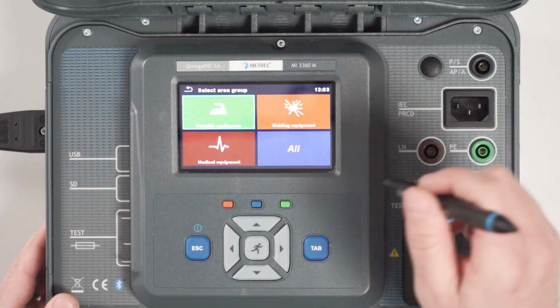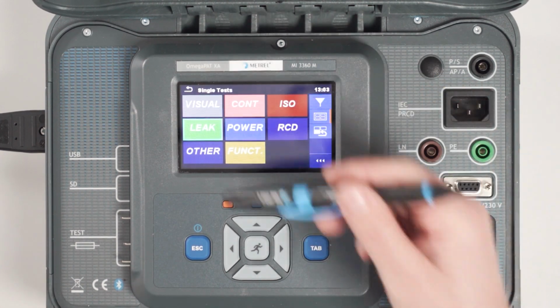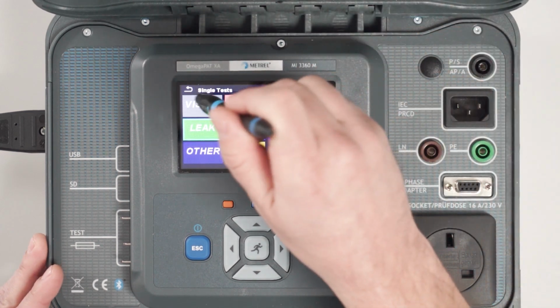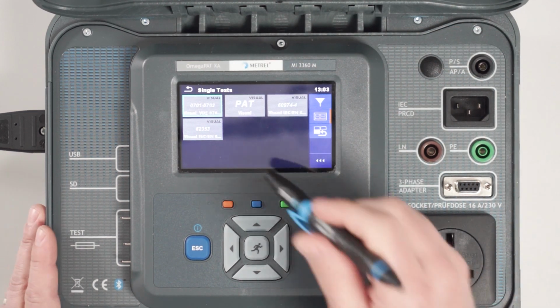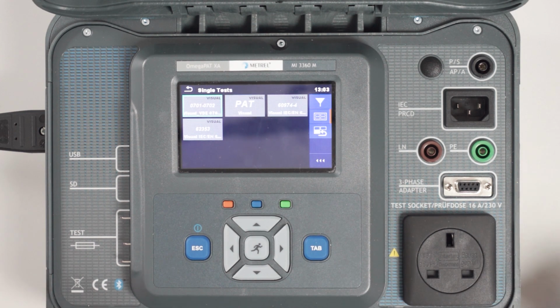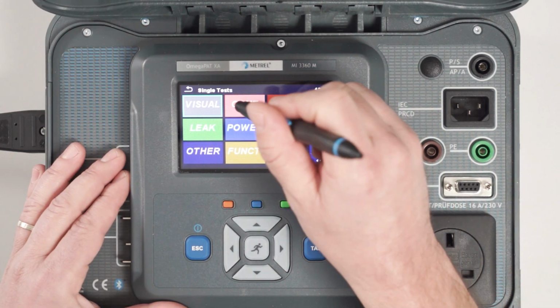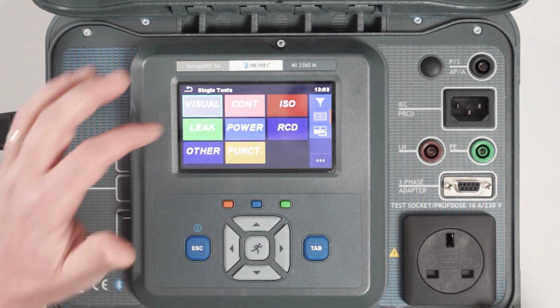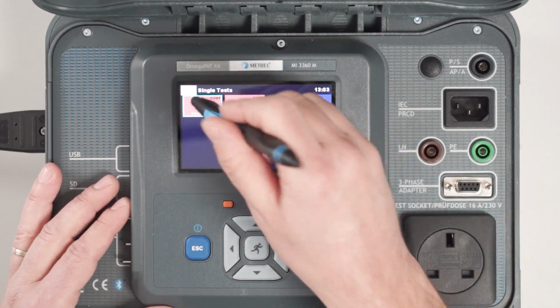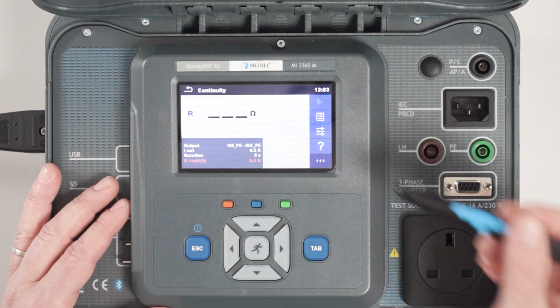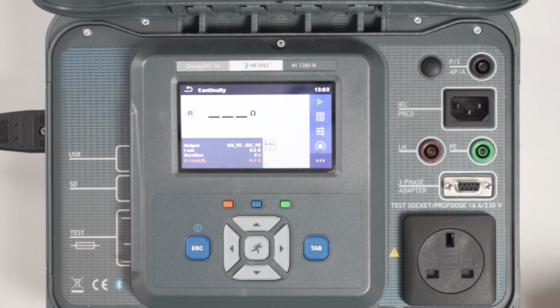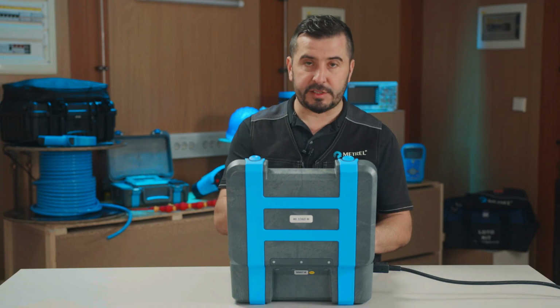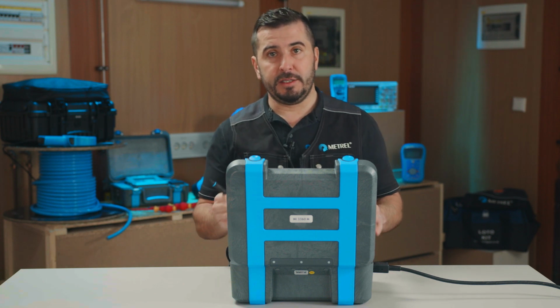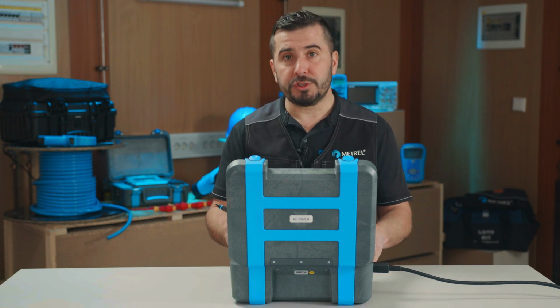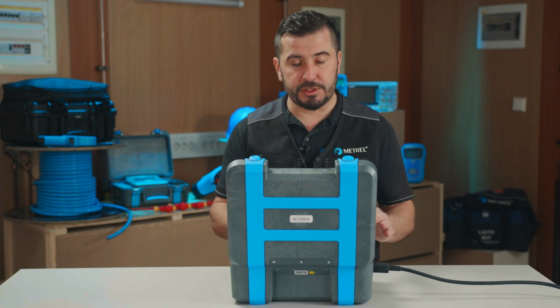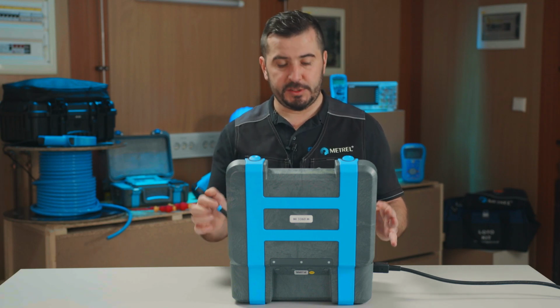Of course, if you return back to all measurements, you will see that we have available pre-designed or predefined visual inspections according to different standards. Then we have the option for testing earth continuity. We can choose here for the earth continuity between different test currents and different test ports. This setup of parameters can be also done inside the Autosequence menu. So before we start Autosequence, we can also adjust all these parameters.